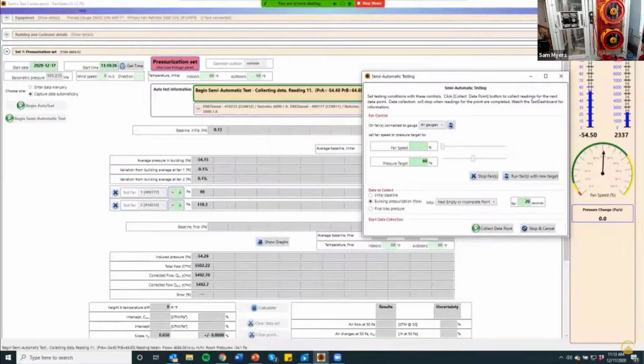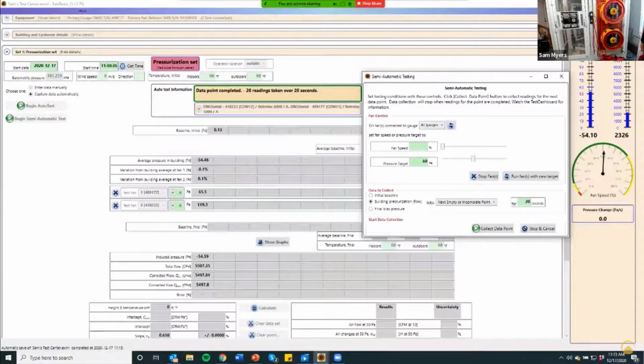I can see the pressure readings here, and I can also see it in the gauge view over here. My fan speed's nice and high, not too high — it's reaching that pressure and staying stable. It says the data point's completed, and it's recorded here in this column. So now I can go down to my next pressure target. I'll tell it to go down to 50, and run fans at the new target.